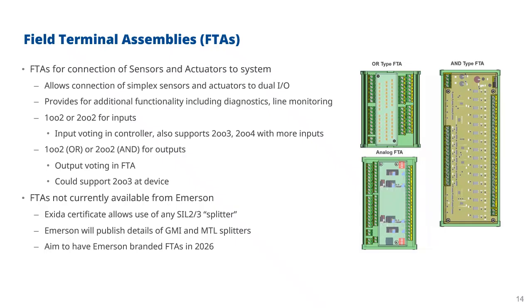So for example, you might have a gas detector or a flame detector, and then the flame detector would go into the safety instrumented system, which would do the processing of the signal, and then there would be an output to your deluge valve or to your emergency shutdown valve, or whatever your application requires. Now, the way that PACSystems SafetyNet works is, to achieve the diagnostics, we have dual I/O. So you have two inputs and you have two outputs.